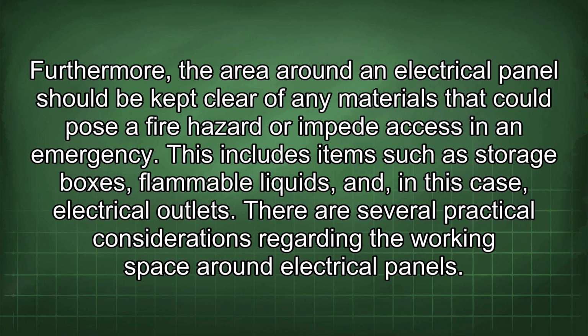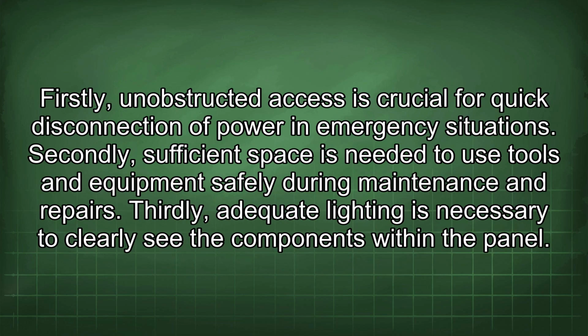Furthermore, the area around an electrical panel should be kept clear of any materials that could pose a fire hazard or impede access in an emergency. This includes items such as storage boxes, flammable liquids, and, in this case, electrical outlets. There are several practical considerations regarding the working space around electrical panels. Firstly, unobstructed access is crucial for quick disconnection of power in emergency situations. Secondly, sufficient space is needed to use tools and equipment safely during maintenance and repairs. Thirdly, adequate lighting is necessary to clearly see the components within the panel.